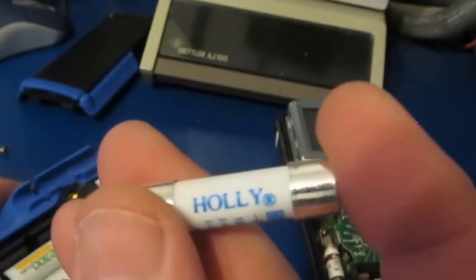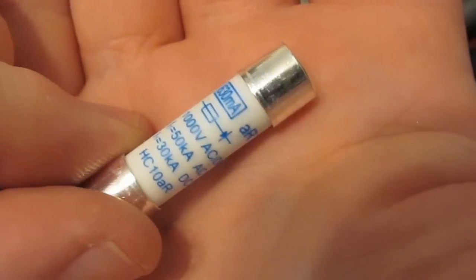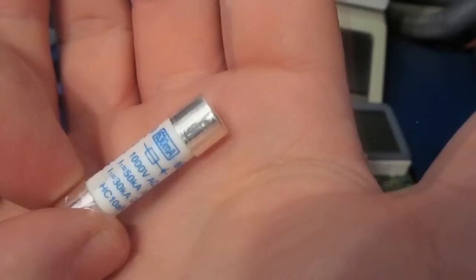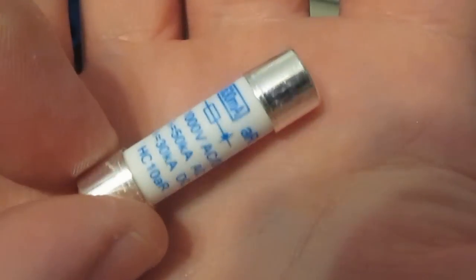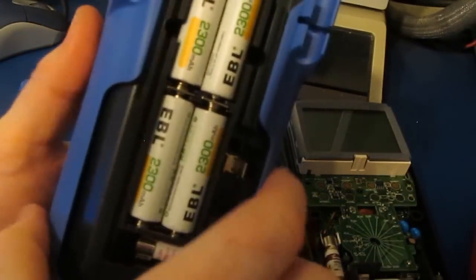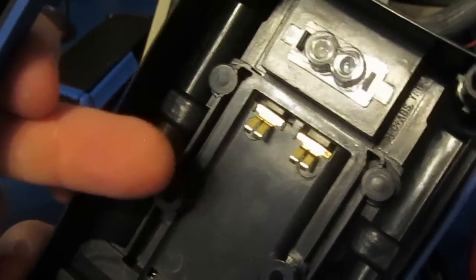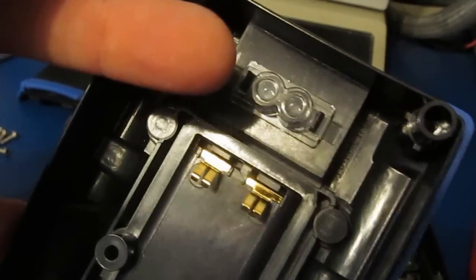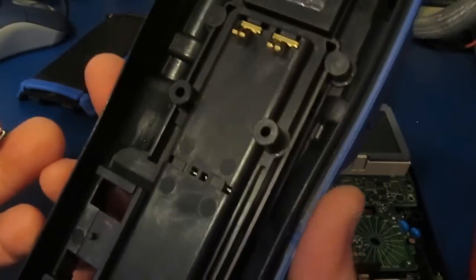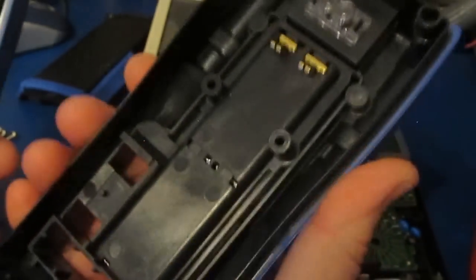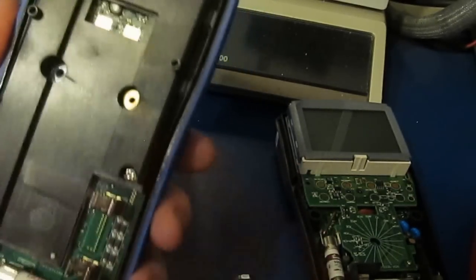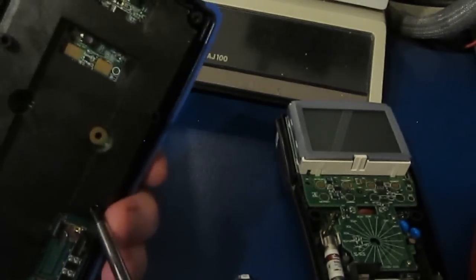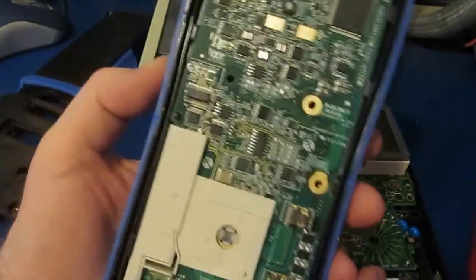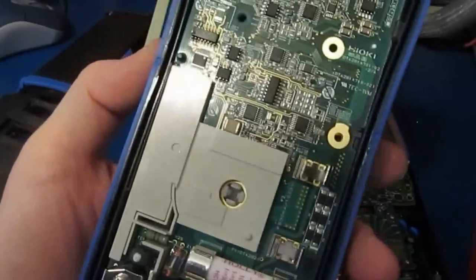So this is the 630 milliamp fuse. Again, this is made by Holly. You can see 1000 volts AC and DC, and the break current is 30,000 amps. Alright, it should just come apart. See how the battery pack attaches. Of course, this is for our optical serial interface. Case is well made. Let's see, now we've got an internal cover. Looks like maybe just one more screw holds this in. This is a busy circuit board.